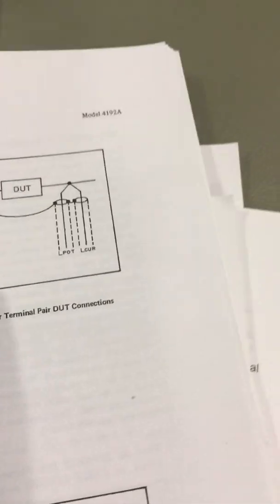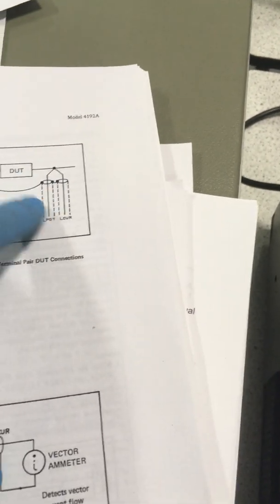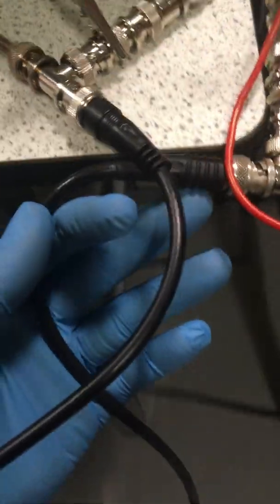If you go to this page, there's a good description about the measurements we're doing. This is the connection that we've got: high current, high potential, low potential, low current—they're connected together. You can see that here, those two pairs are connected together.